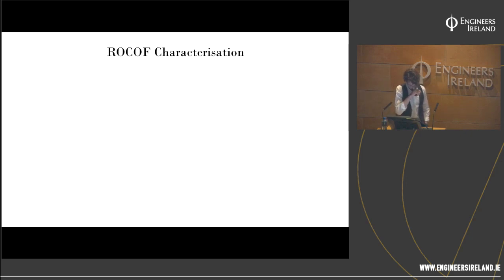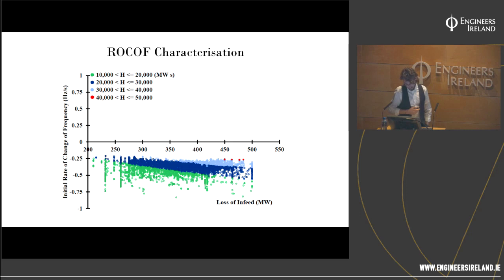What I'm going to show you is a scatter plot, and each dot represents a simulation, the loss of a contingency. I've looked at the inertia online and the size of the generator that was lost in that instance. This is for in-feeds, so it's a generator or an HVDC import, so it's a negative rate of change of frequency. You can see there are two things at play. As the contingency increases, we get extreme RoCoFs, and also as the inertia declines, from red to light blue to dark blue to green, we get more extreme behavior as well.